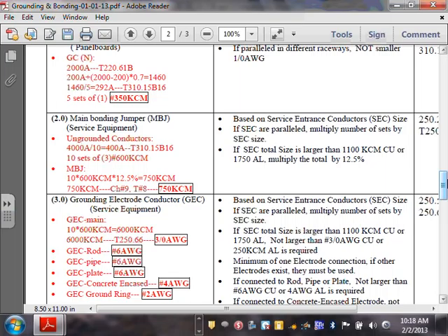Okay, so here's my point. In order to size the main bonding jumper, guys, you have to size the service conductors. We did. Right here, you're looking at it. Then for the main bonding jumper, the code says you have to go by this when you parallel. Right here, based on the service conductor, if you parallel, then multiply the sets by the service entrance conductor size, and if the service entrance total is larger than 1100 kcmil for copper, or aluminum, God forbid, you're pulling aluminum here, then 12.5%. If it's not larger than these two numbers, what do you do? You go to Table 250.66 directly from there. Only multiply by 12.5% if the total is larger than these two numbers. Everybody knows that? And then you came up with 750.